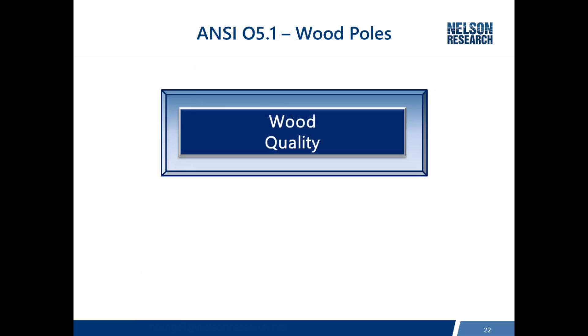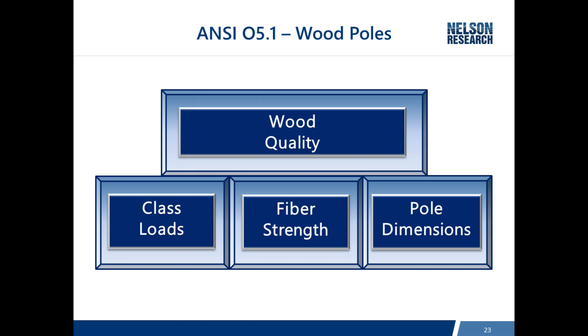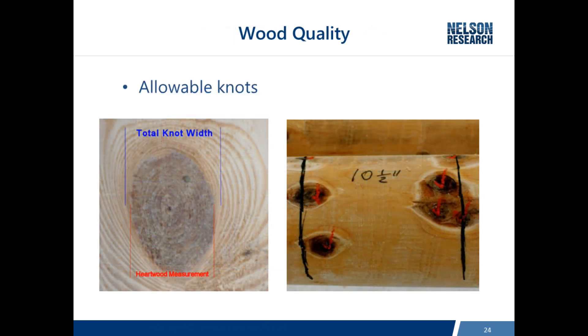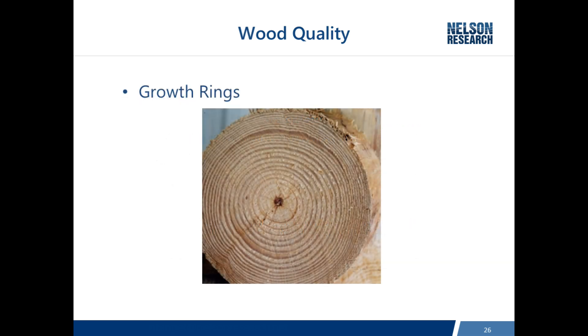ANSI O5.1 addresses four functions or qualities about wood poles. The first is wood quality. The standard also establishes class loads — you've heard of class 3, class 4 — which refer to a horizontal load applied two feet from the tip. Fiber strength is the strength of each species of pole; because species differ in strength, the pole dimensions are adjusted so that different species support the same class loads. Examples of wood quality criteria include allowable knots, sweep in a pole, and number of growth rings per inch.